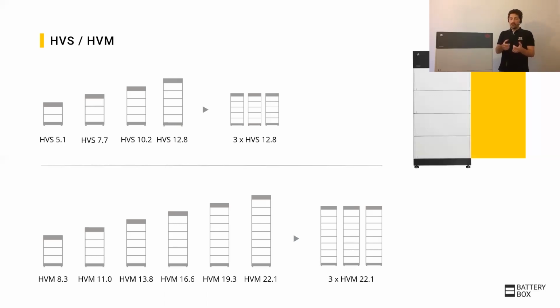An HVM module has a slightly higher capacity of 2.76 kilowatt hours, but, and that's also a big difference, only a voltage of 50 volts, so about half the voltage of the HVS. That's why it's only possible to start with 3 modules with a minimum voltage of 150 volts and a capacity of 8.3 kilowatt hours. But then it's possible to add more modules in one tower, up to 8 modules, which would again be about 400 volts and a pretty high capacity of 22 kilowatt hours.